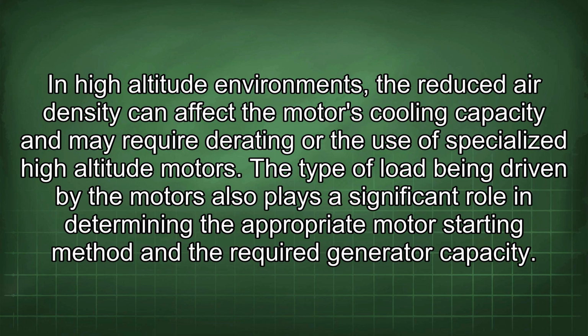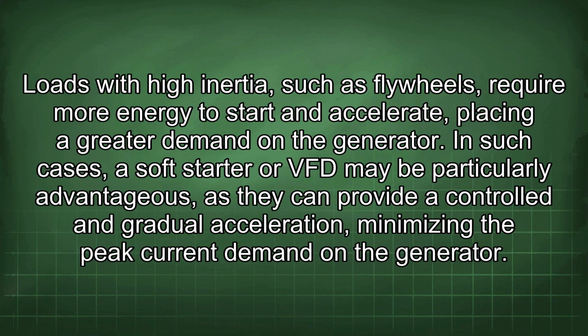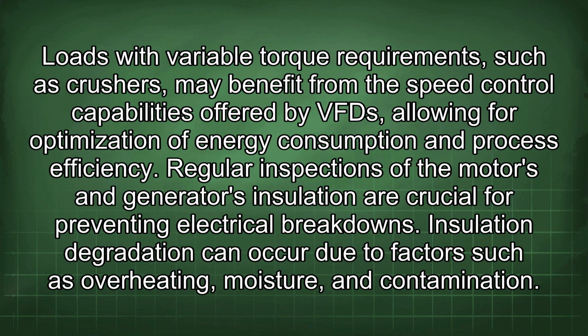of specialized high-altitude motors. The type of load being driven by the motors also plays a significant role in determining the appropriate motor starting method and the required generator capacity. Loads with high inertia, such as flywheels, require more energy to start and accelerate, placing a greater demand on the generator. In such cases, a soft starter or VFD may be particularly advantageous, as they can provide a controlled and gradual acceleration, minimizing the peak current demand on the generator. Loads with variable torque requirements, such as crushers, may benefit from the speed control capabilities offered by VFDs, allowing for optimization of energy consumption and process efficiency.